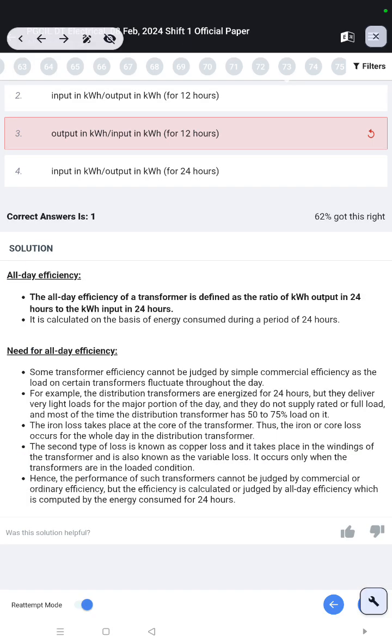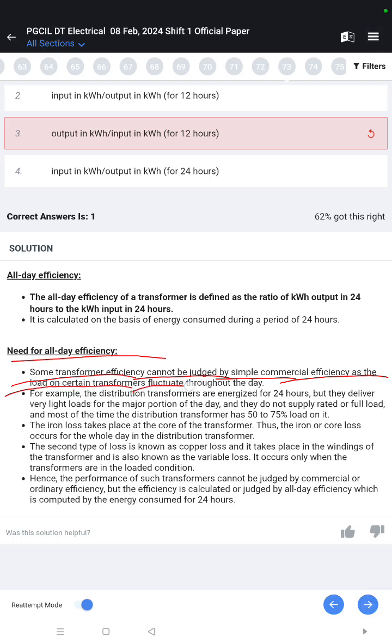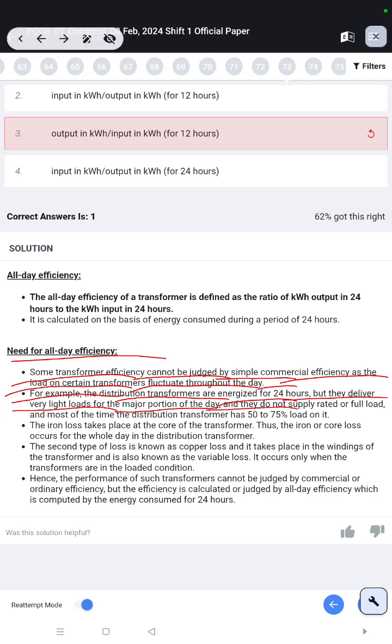Some transformer efficiency cannot be judged by simple commercial efficiency as the load on certain transformers fluctuates throughout the day. For example, the distribution transformers are energized for 24 hours but they deliver very light loads for the major portion of the day and they do not supply rated or full load. And most of the time the distribution transformer has 50 to 75% load on it.